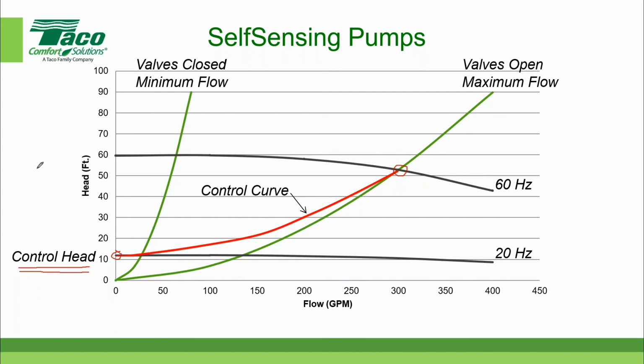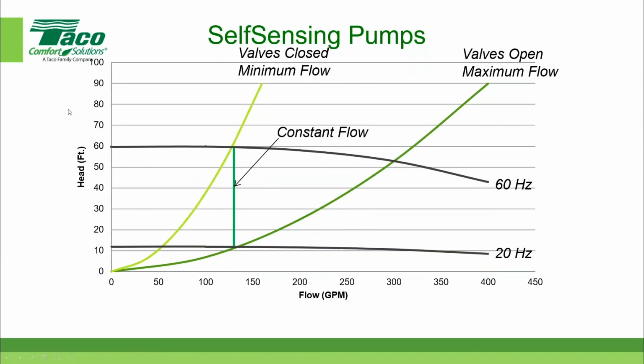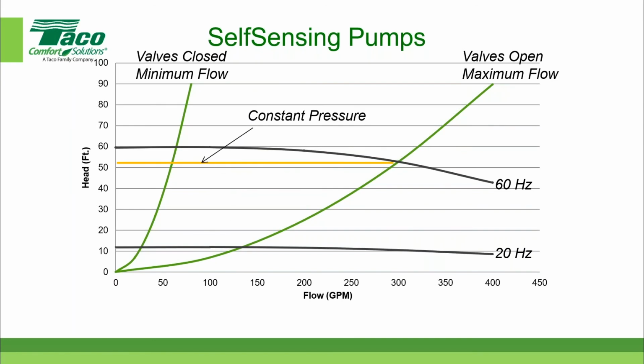Okay, because it's controlled by software, we not only can have a variable flow, variable speed functionality, but we can also have constant flow, variable speed. And the third mode of operation is to have constant pressure differential and variable speed. All three of these control functions are embedded in the drive. So when you specify a self-sensing pump, you can tell us whether you want variable speed, variable flow, or variable speed, constant flow, or variable speed, constant differential pressure. The default, when it leaves the factory, is variable flow, variable speed. And that's where you get the control curve that goes from minimum to maximum.